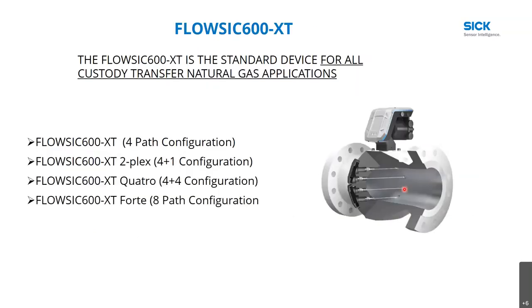Now, here's the first meter we're going to talk about today. This is the 600 XT. This is the new generation of SICK ultrasonic meter. This one that you see here is a four-path configuration. You can see on the meter here, we have one transducer here and one across here. So we're sending sound waves back and forth, and measuring the velocity across this cross-sectional area. This four-path model has four pairs of transducers mounted across four cross-sectional areas. So we're measuring the velocity across these four cross-sectional areas, taking a weighted average of that velocity times the inner diameter to calculate how much volume is going through the meter.